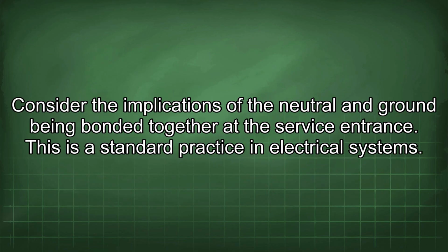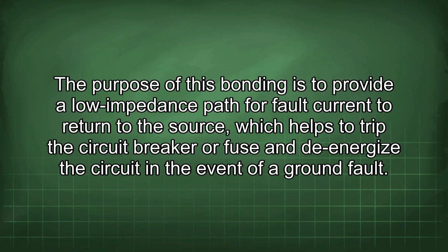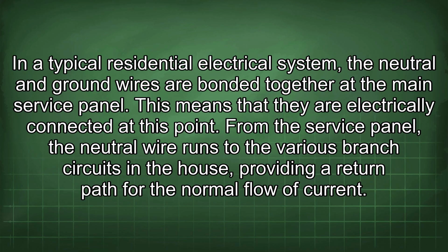Consider the implications of the neutral and ground being bonded together at the service entrance. This is a standard practice in electrical systems. The purpose of this bonding is to provide a low impedance path for fault current to return to the source, which helps to trip the circuit breaker or fuse and de-energize the circuit in the event of a ground fault. In a typical residential electrical system, the neutral and ground wires are bonded together at the main service panel. This means that they are electrically connected at this point. From the service panel, the neutral wire runs to the various branch circuits in the house, providing a return path for the normal flow of current.